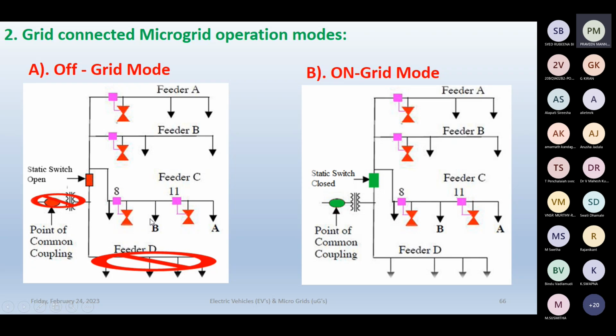But here, there is a static switch between feeders A, B, C and feeder D. When the grid is not connected, the static switch will be open, meaning feeder D is supplied from the main grid only. The feeder A, B, C generation does not supply feeder D, so simply it is not a prioritized load.